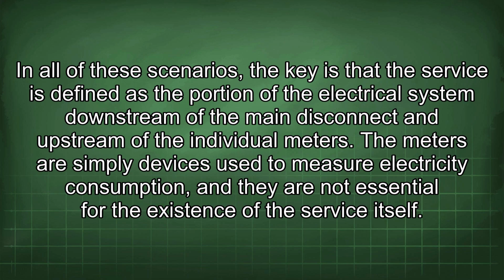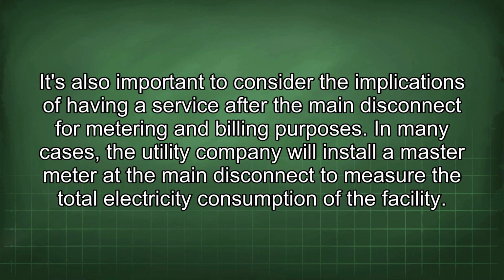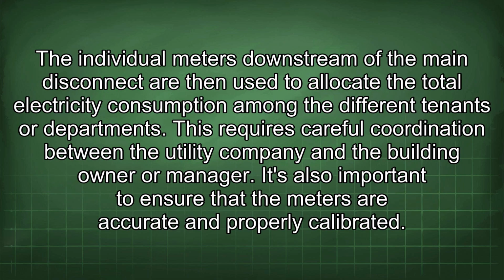service itself. It's also important to consider the implications of having a service after the main disconnect for metering and billing purposes. In many cases, the utility company will install a master meter at the main disconnect to measure the total electricity consumption of the facility. The individual meters downstream of the main disconnect are then used to allocate the total electricity consumption among the different tenants or departments. This requires careful coordination between the utility company and the building owner or manager.